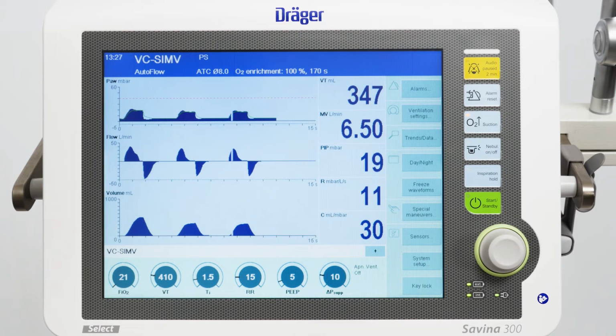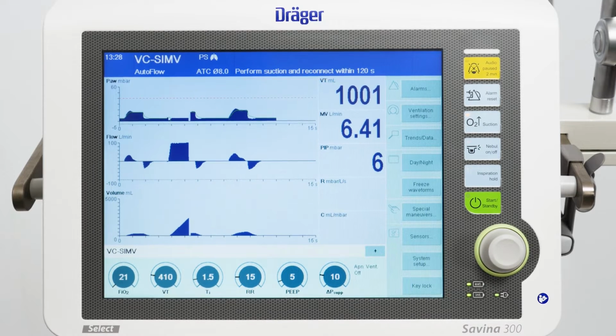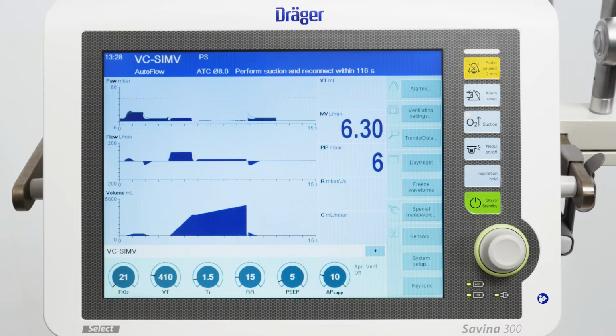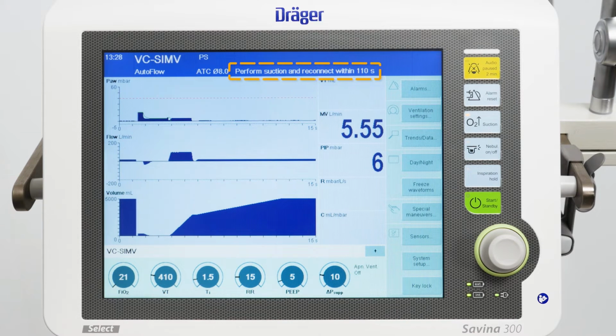Within 180 seconds, Savina 300 Select expects a disconnection for suction. In the header bar, the initial oxygen enrichment phase is displayed with the remaining time. Disconnect the patient and perform the suction maneuver. 120 seconds are available for suctioning. In the header bar, the disconnection phase is displayed with the remaining time.